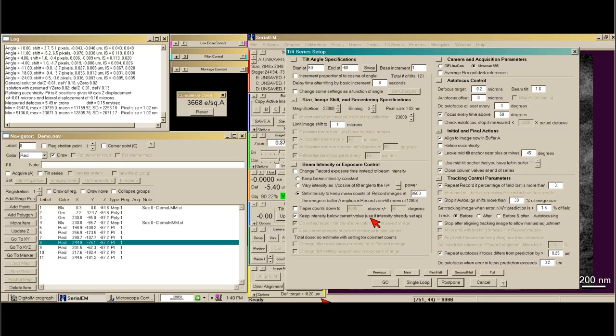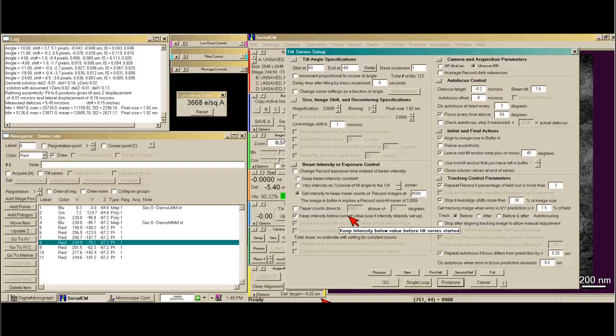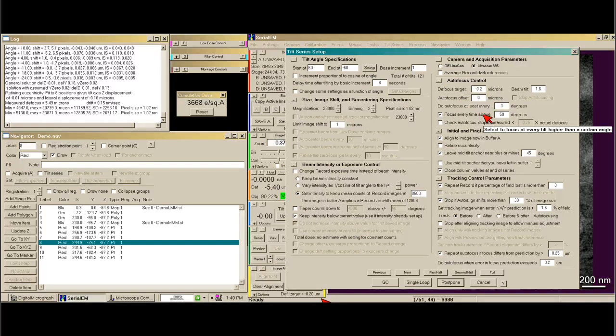I like to say 'keep intensity below current value.' What I've done is set up the beam to be a certain size, which gave me almost 13,000 counts. When I tick this box, the beam will never get smaller, which means it will not accidentally come into my image area. Then we can pick our defocus target — for plastic, we like to be just below focus. We can tell it to focus every so many degrees, as well as focus at very high tilts; in this case, every time above or below 50 degrees.